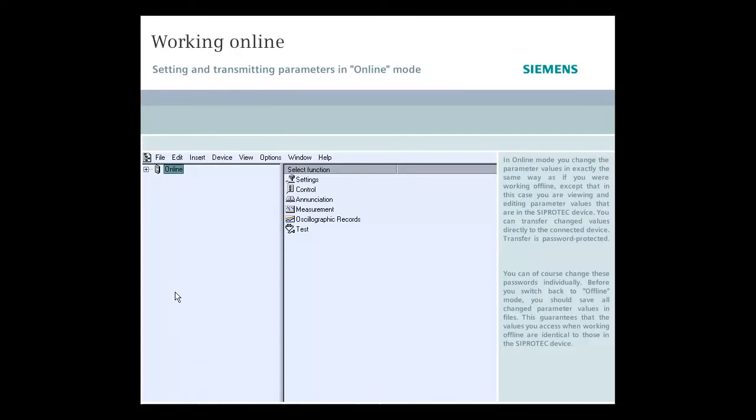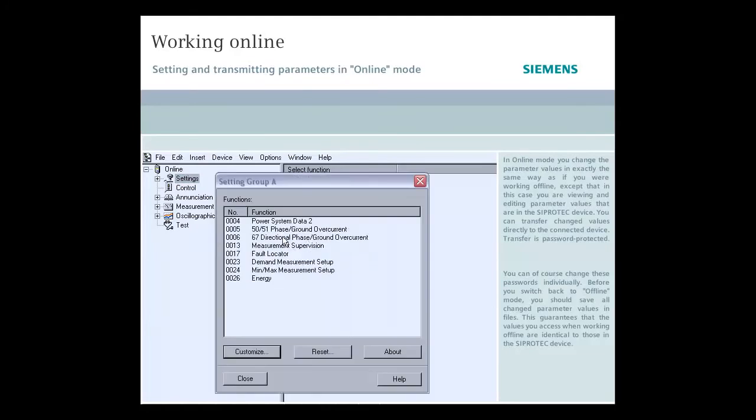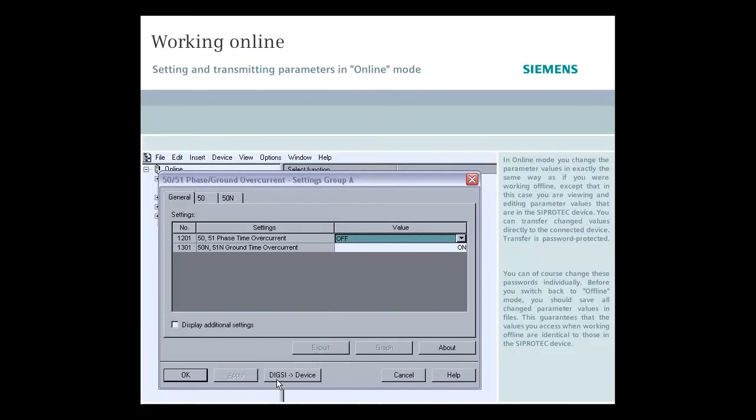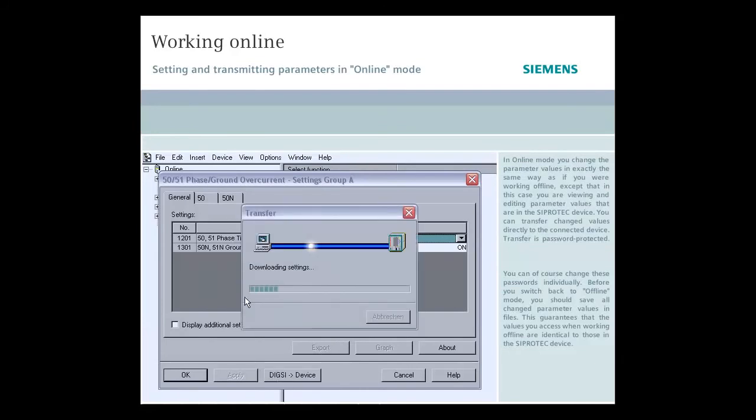In online mode, you change the parameter values in exactly the same way as if you were working offline, except that in this case you are viewing and editing parameter values that are in the SIPROTEC device. You can transfer changed values directly to the connected device. Transfer is password protected. You can, of course, change these passwords individually.